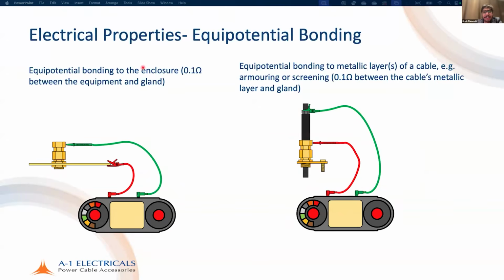The electrical properties of the glands are also very rigorously tested. For example, equipotential bonding between the enclosure and the gland is tested, and this value has to be below 0.1 ohm. Also, the bonding, the continuity between the armor of the cable and the gland is tested, and this has to be below 0.1 ohm. So the gland, the earth tag, everything is correctly tested according to this requirement if you choose a gland conforming to 62444.